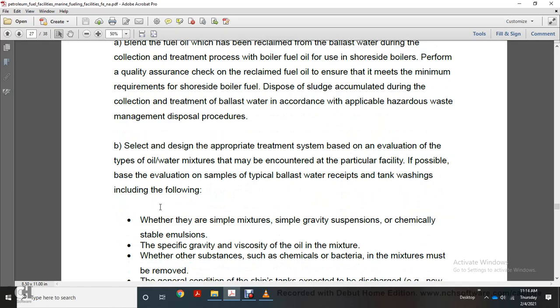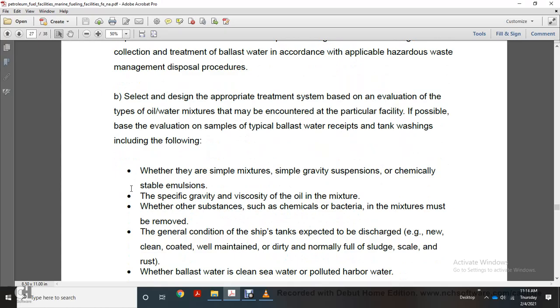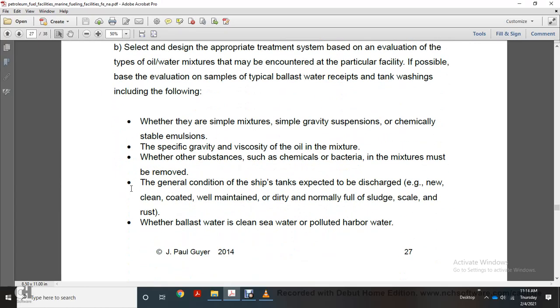Select and design an appropriate treatment system based on an evaluation of the types of oil mixture and oil-water mixture encountered at a particular facility. If possible, base the evaluation samples on the type of ballast water, grade, receipt, and tank washing. Include the following: whether simple mixtures or simple gravity suspensions, chemically stable emulsions, specific gravity, viscosity of the oil mixture, and whether other substances such as chemicals, bacteria, and mixtures must be removed.